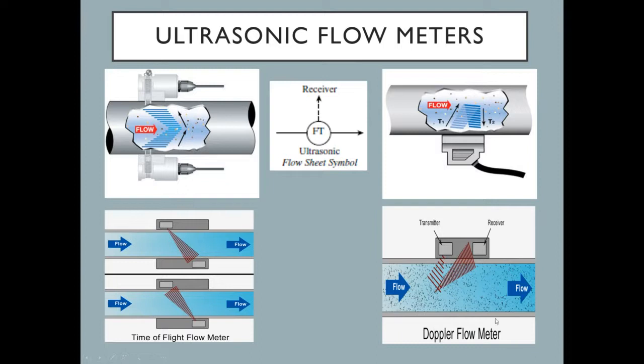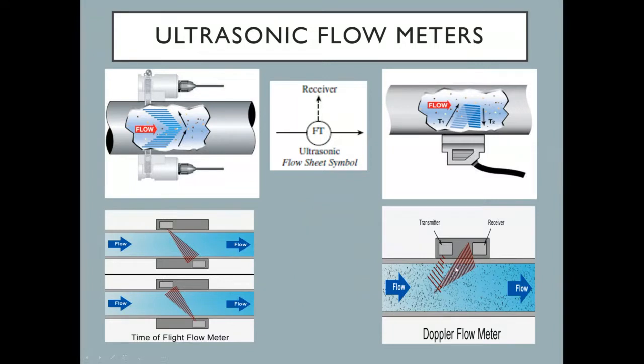The second style, shown on the right, is called a Doppler flow meter. It still uses a transmitter and receiver, but the major difference is that Doppler flow meters rely on particles, suspended solids, or bubbles within the flow stream to reflect the ultrasonic sound wave back to the receiver. Time-of-flight is generally used for clean flow applications, whereas Doppler flow meters actually require suspended solids, particles, or bubbles in the flow stream.